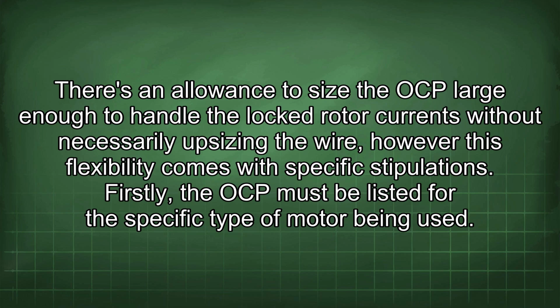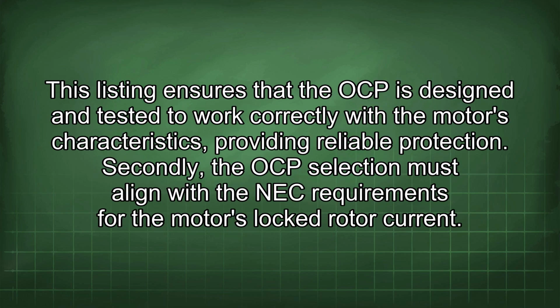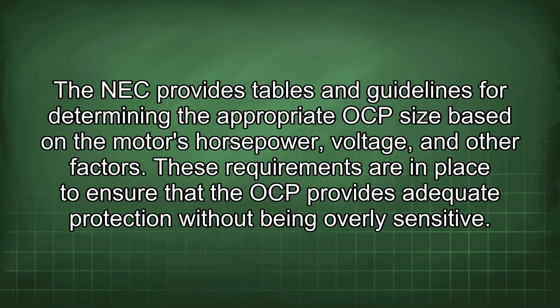Firstly, the OCP must be listed for the specific type of motor being used. This listing ensures that the OCP is designed and tested to work correctly with the motor's characteristics, providing reliable protection. Secondly, the OCP selection must align with the NEC requirements for the motor's locked rotor current. The NEC provides tables and guidelines for determining the appropriate OCP size based on the motor's horsepower, voltage, and other factors. These requirements are in place to ensure that the OCP provides adequate protection without being overly sensitive.